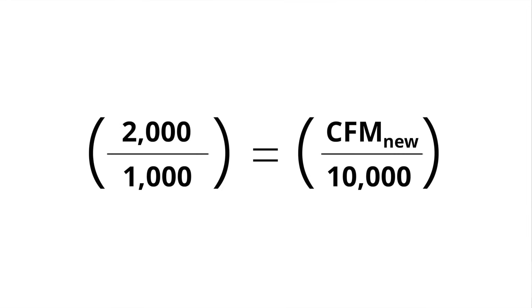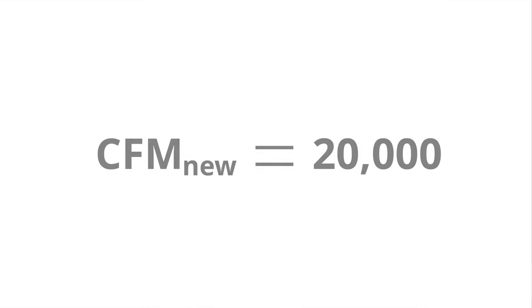As a numeric example, let's say we have a fan running at 1,000 RPM, moving 10,000 cubic feet per minute, while generating 10 inches of water gauge in static pressure, at 100 brake horsepower. In our example, we'll double the speed from 1,000 RPM to 2,000 RPM. The equation is: 2,000 RPM divided by 1,000 RPM equals the new CFM, X, divided by the old CFM, 10,000 — which solves for a new flow of 20,000 CFM.